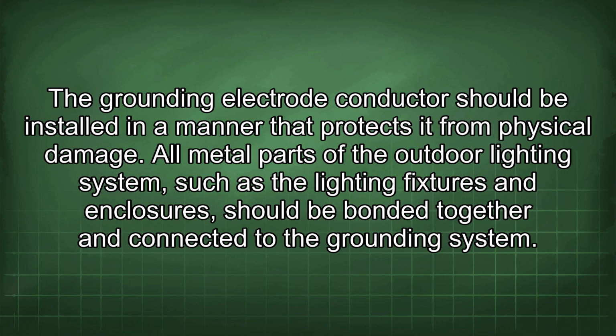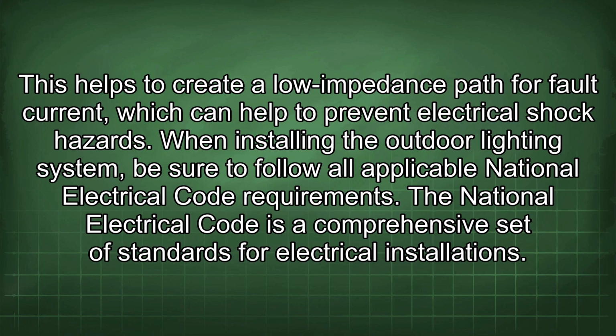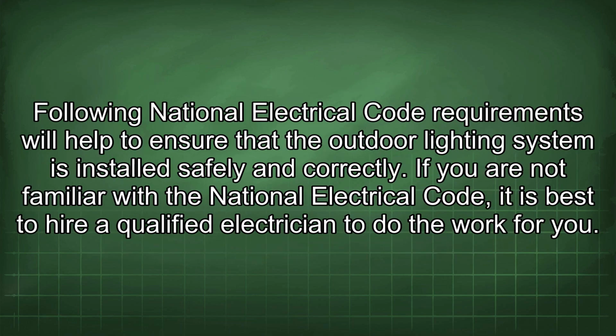All metal parts of the outdoor lighting system, such as the lighting fixtures and enclosures, should be bonded together and connected to the grounding system. This helps to create a low impedance path for fault current, which can help to prevent electrical shock hazards. When installing the outdoor lighting system, be sure to follow all applicable National Electrical Code requirements. The National Electrical Code is a comprehensive set of standards for electrical installations. Following National Electrical Code requirements will help to ensure that the outdoor lighting system is installed safely and correctly.